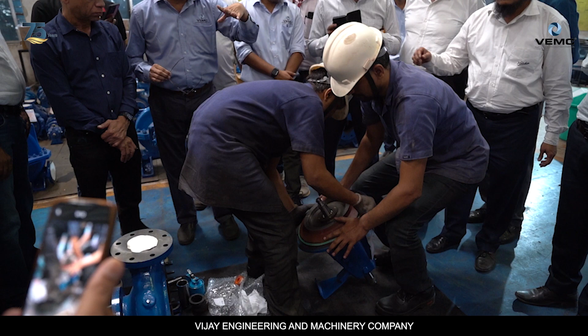They are showing the fitment. With a gland pack, you apply a seal to arrest leakage and prevent water from spilling out of the pump. What we now generally suggest is a drip tray arrangement at the bottom with an exit, which can be drained into the sump in the pump room, or exited outside if the pump is on ground level. The whole idea is simple: the drip tray takes care of everything and makes it easier to manage.